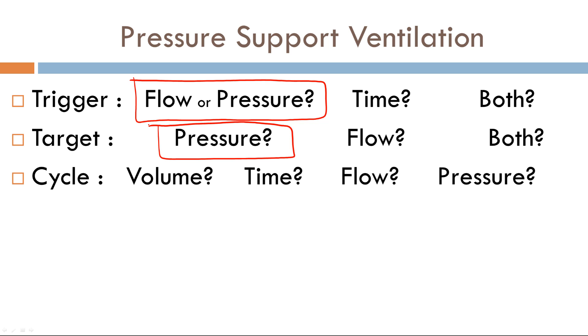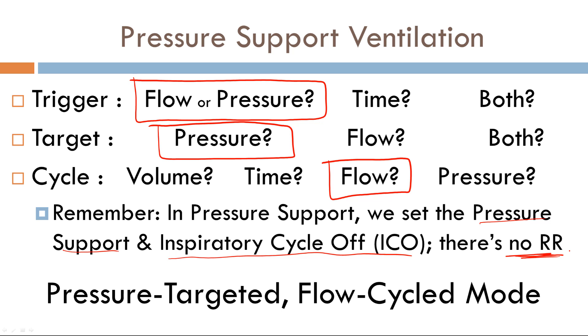The cycle variable in pressure support ventilation is flow — specifically the inspiratory cycle-off (ICO). After the flow reaches a certain percentage of the peak inspiratory flow, the breath cycles off. We set the pressure support (target variable) and the inspiratory cycle-off percentage (flow cycle). There is no set respiratory rate; all breaths are triggered by the patient. Pressure support ventilation is a pressure-targeted, flow-cycled mode.